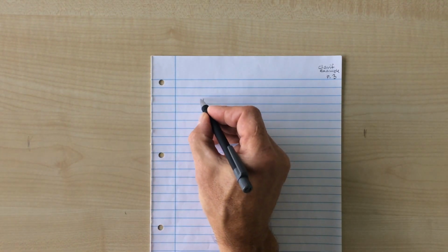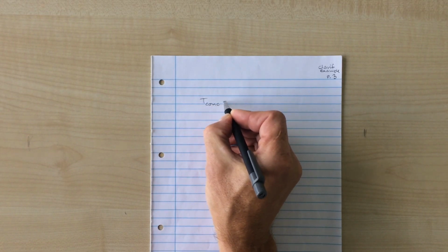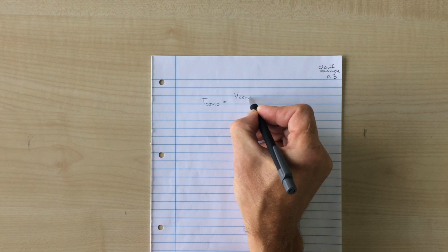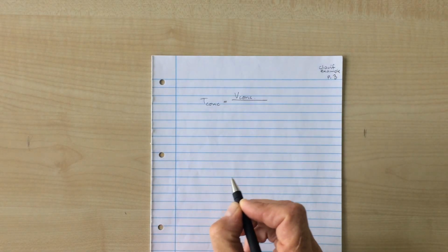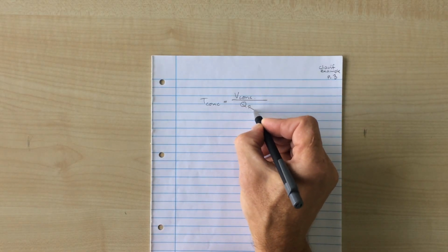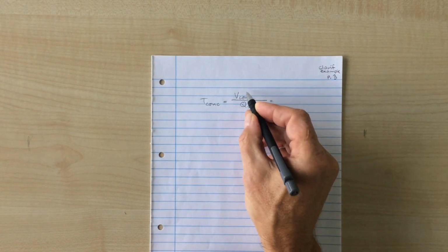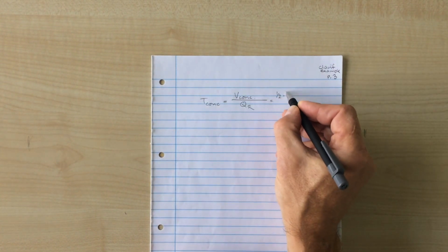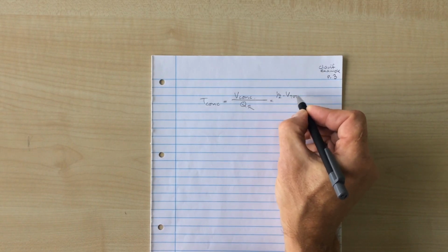This concentration time is then equal to the concentration volume of the clarifier divided by the flow going out. And the volume that I would allow the sludge to concentrate in would be half of the total volume of the clarifier.